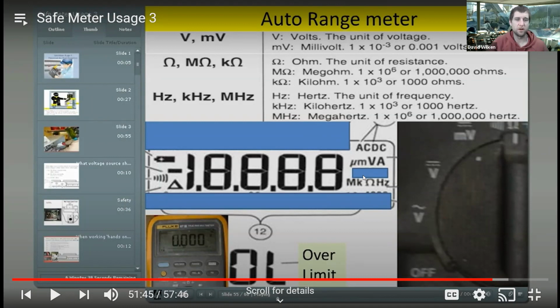I'm not sure what you're looking at there, but on that range switch, you got your volts AC, volts DC, then there's a millivolts above that on your range switch there. There you go. Just to the left of that is your millivolts. Okay. So those actually don't do what you just said. That's how mine is too. You have to set it for millivolts. It won't read millivolts on volts. But mine will switch between AC and DC. My millivolts just defaults on AC. So then you have to push a button to make it switch to DC millivolts.